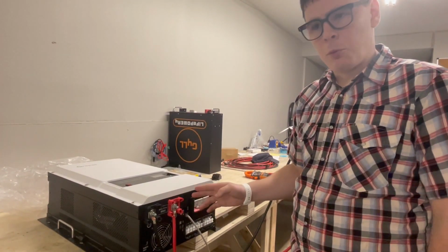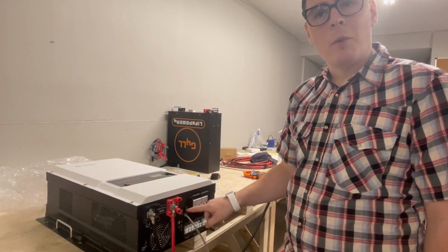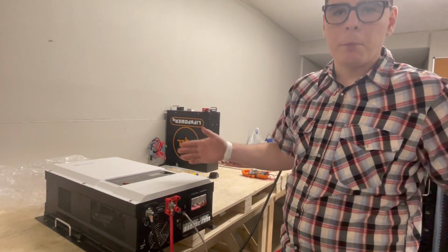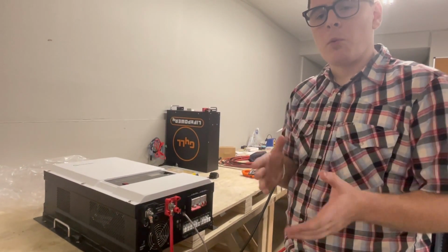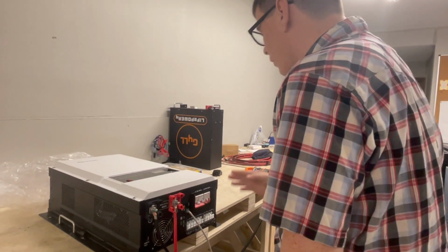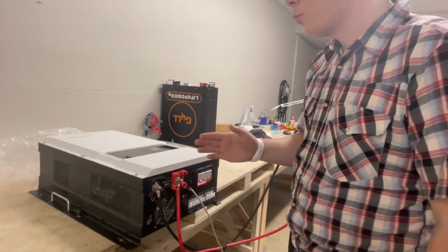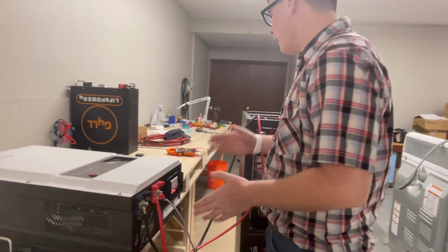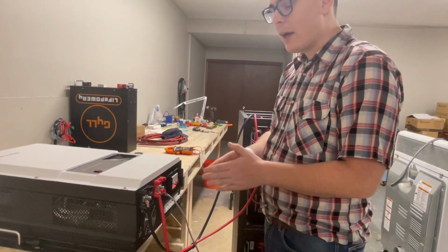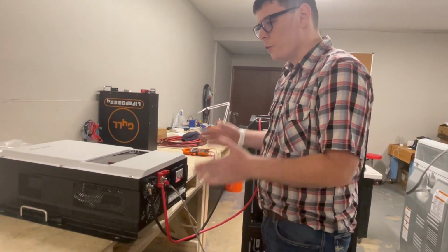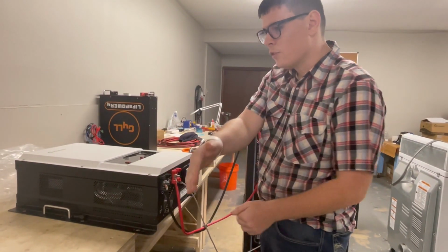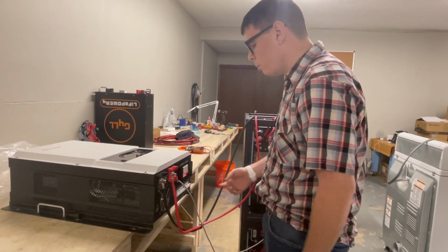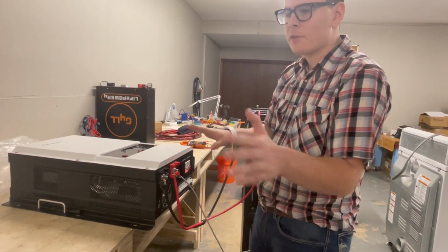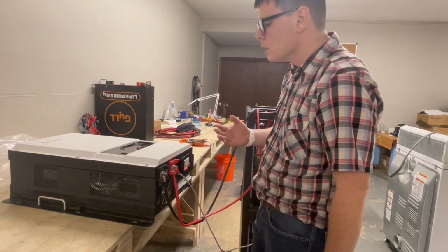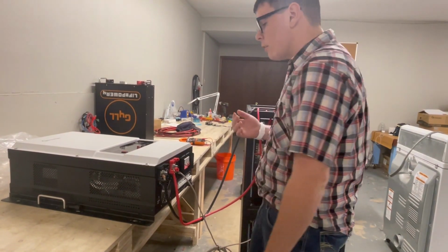The RS-485 port is wrong on the 12 kilowatt. It is right on the stackable inverters. That is the port that you're going to use to communicate. So the other thing that you'll always want to think about as well is our CAN hub that we have. If you had multiple stackable inverters, you could just plug in each inverter to that hub. It's $29. You plug in the batteries into the hub and then every inverter into the hub. And that was in our other video as well for the stackable units.